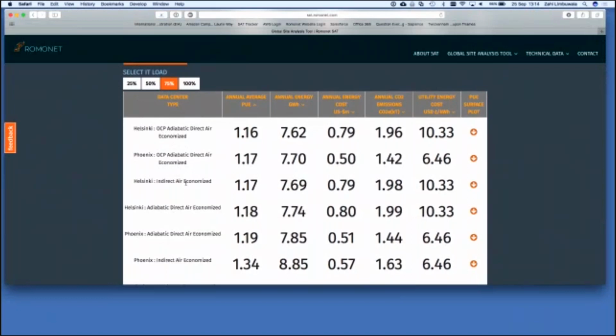The difference primarily is on the electrical system, with the OCP system based on the V2 racks. So it's pretty simple to use. We've got a utilization selector at the top here, so this is basically saying my one megawatt data center, averaging a 75% loading from a capacity perspective of that one megawatt, so around 750 kilowatts of load.